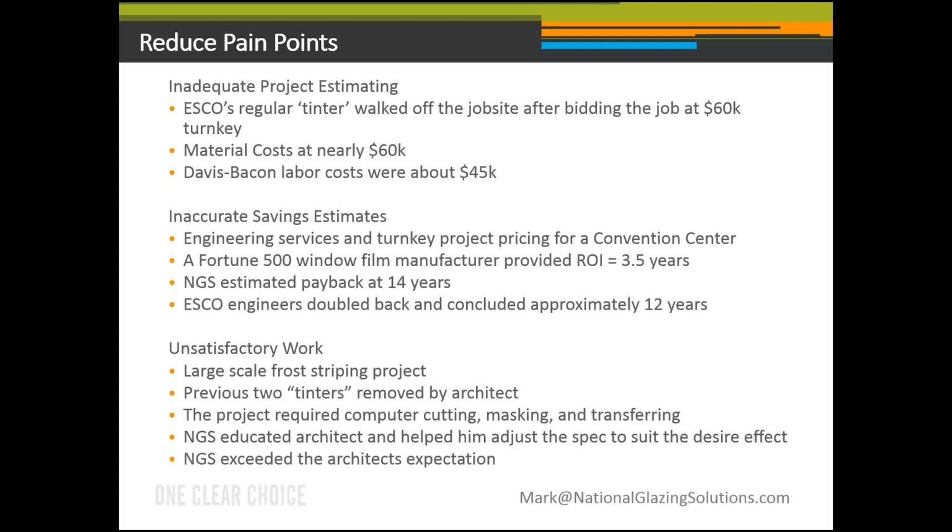The second example is an ESCO brought an opportunity to us to provide engineering services and turnkey project pricing for a convention center. A window film manufacturer had provided the ESCO with estimated payback from energy savings at 3.5 years using eFilm. Using eQuest and much more appropriate building shells and HVAC efficiencies and occupancies, we put the payback at 14 years.